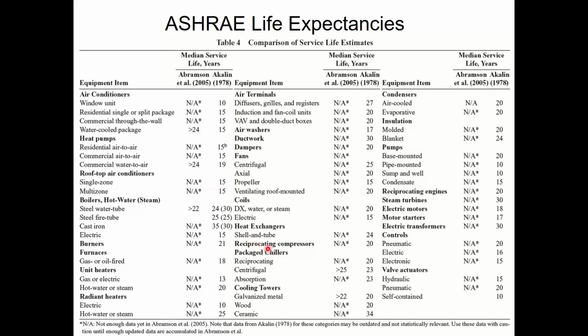For you guys that have boilers out there, if you have large cast iron boilers, which would be more likely to be found in small commercial buildings, getting like 30 years out of it is not abnormal at all. More commercial type boilers that are typically and historically steel, you're probably talking about 25 years for the boiler, right? So as those boilers get older, time to start looking at replacing those guys. Furnaces at your house or in your commercial building, furnaces are very common to see in a commercial building, or the gas furnace that is inside the rooftop air conditioner, right? That furnace, that gas-fired rooftop, 18 years is kind of the limit. And on a rooftop unit, it's probably going to be less. 18 years is more when I have indoor-based equipment. And at that point, you should be looking at getting a new rooftop.